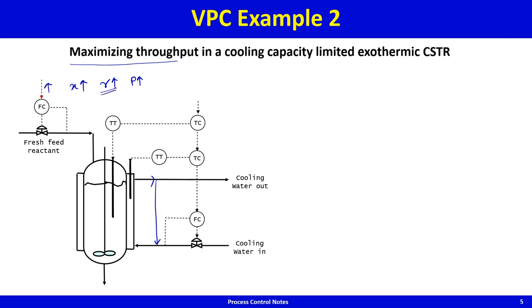As the reaction rate increases in this exothermic system, the heat released due to reaction also increases. To maintain reactor temperature, the coolant valve opening must also go up. As we increase throughput, this coolant valve maxes out — it becomes fully open — meaning there is no more reaction heat removal capacity. If we keep increasing feed beyond this point, reactor temperature control is lost.